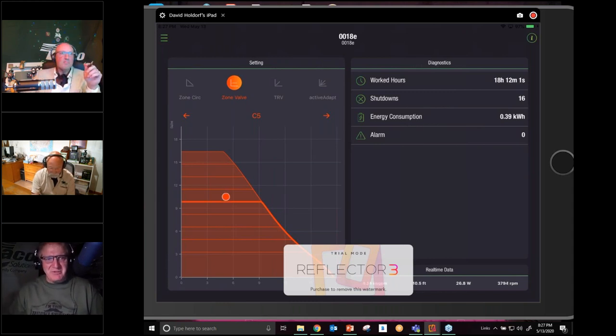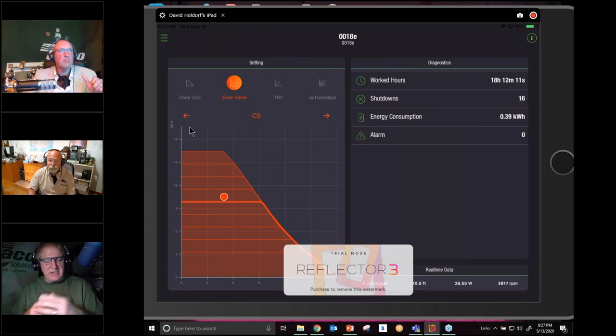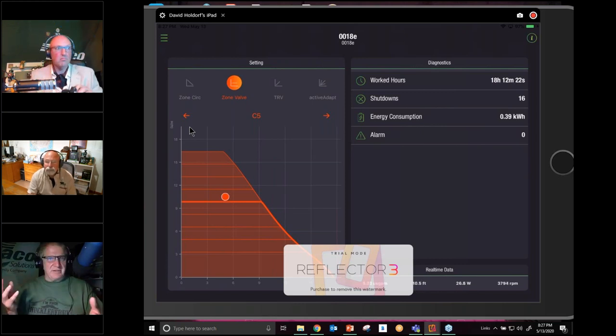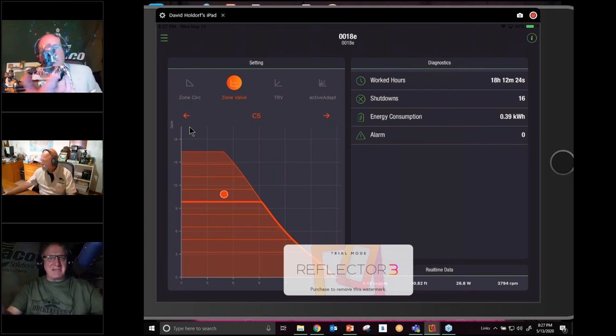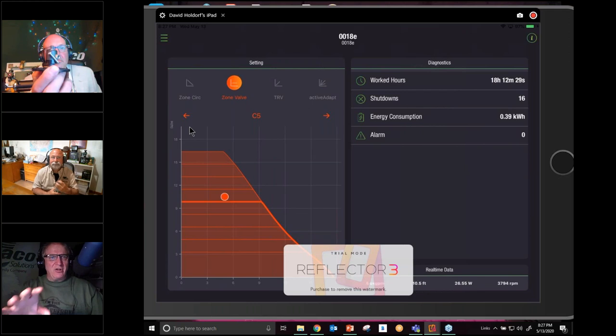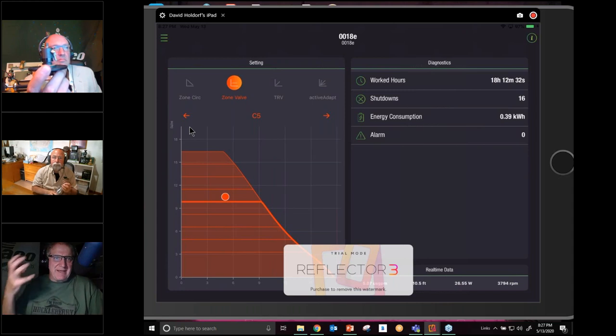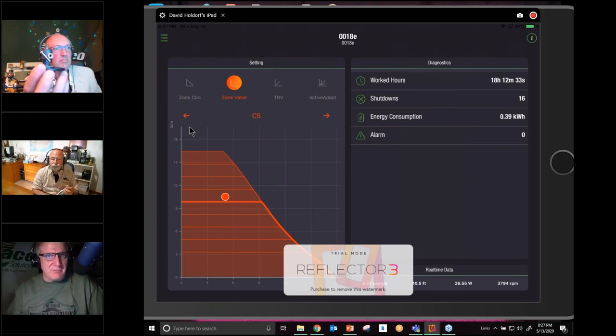There you go. ECM pumps and ferrous metals. Is it affecting pump life expectancy? Asked Gordon Ramberg. Not ours. Not ours. We talked a little bit about it last week, Gordon. We'll mention it again. The concern about ECM pumps is that ECM is an electronically commutated motor. The part that makes that happen is a permanent, always-on magnet. And you see Dave holding it right up there with some screws connected to it. That's a permanent rare-earth magnet that's in there. And that does half the work of the system already, so we don't have to create the magnet. So that's one of the reasons it uses less electricity.